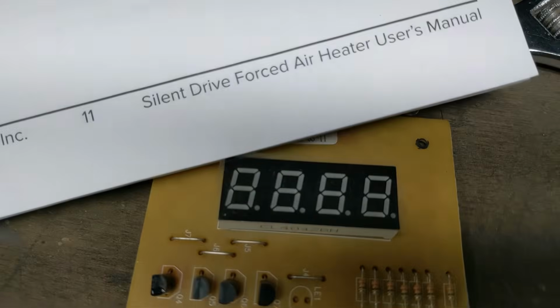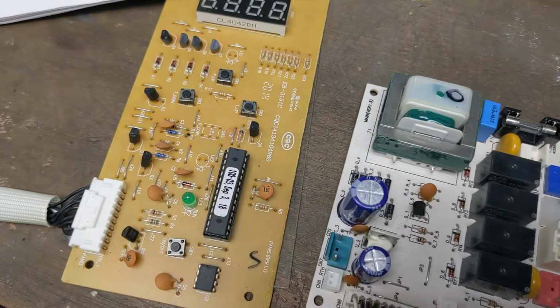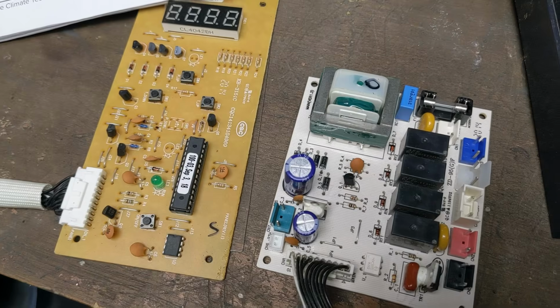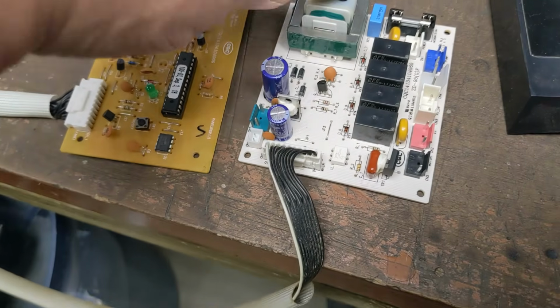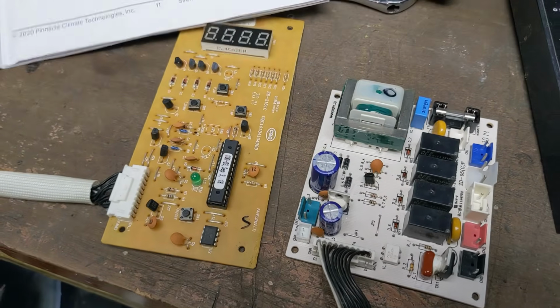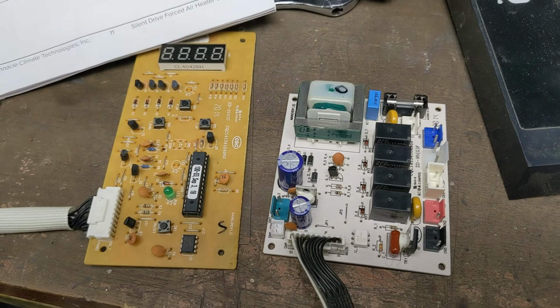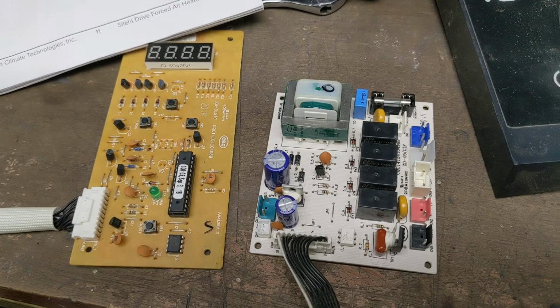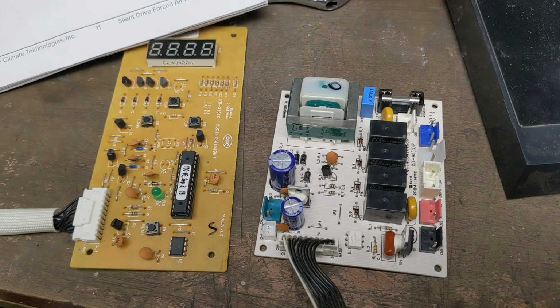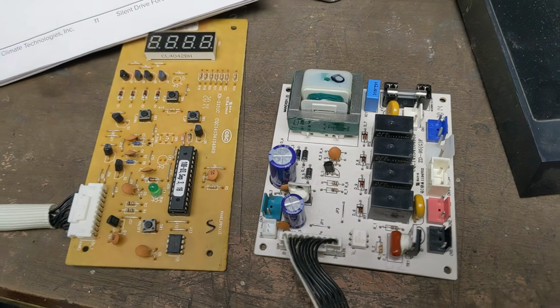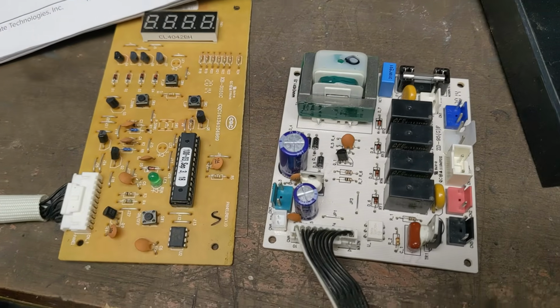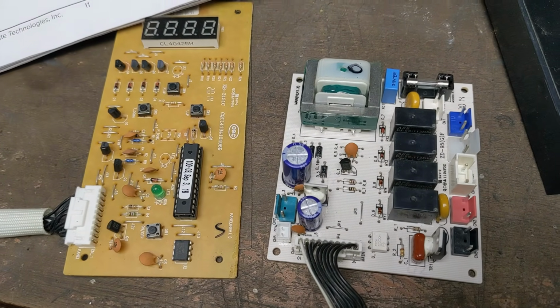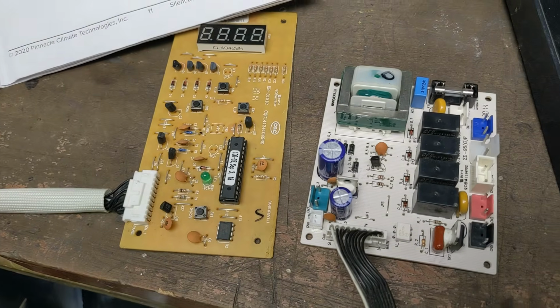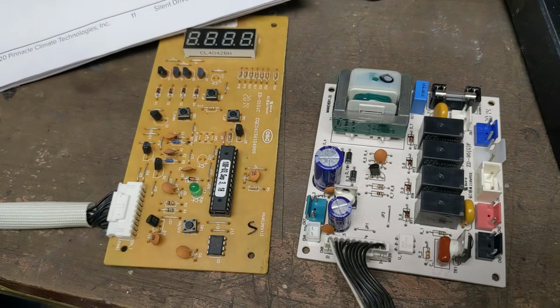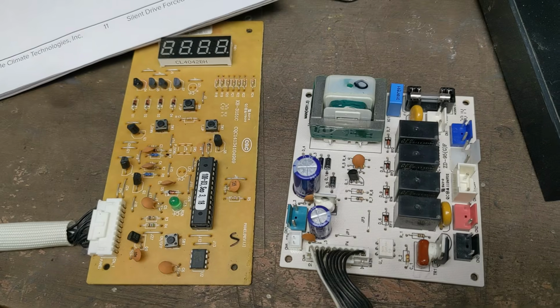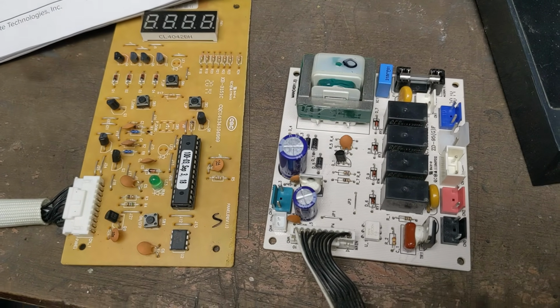The display functions correctly. It gives you temperature, and you can see the safety checks, and then you just get code E1. So somehow this is not getting the signal it needs telling it that the flame is lit and running correctly, and then it's not thermally overloaded with that temperature sensor. That's it, there's no other sensors on the machine. So something on this board, and all the wire connections to get to the board to tell it what those sensors are seeing, is fine.